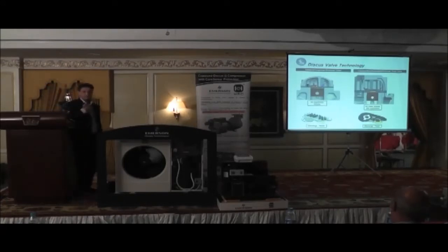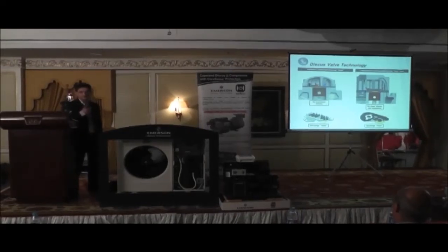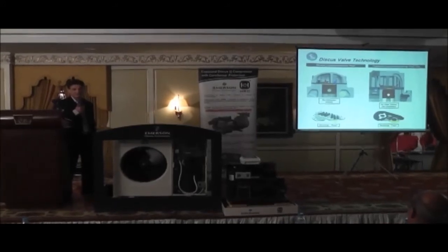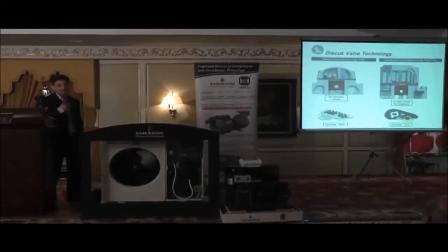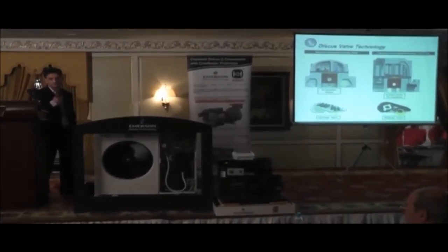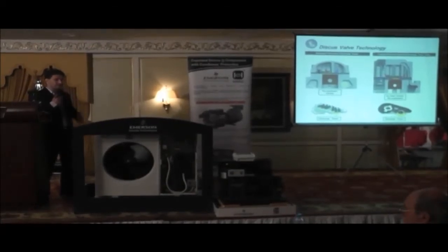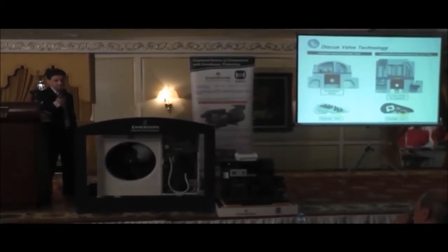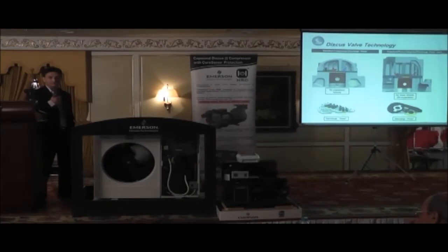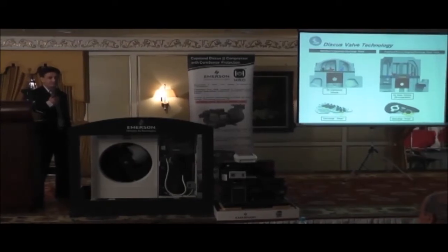So on your left-hand side, we have a standard reed compressor. On the right-hand side, the discus. The main difference between the two is that with the discus compressor, we introduce the refrigerant into the cylinder via the valve plate. So the valve plate is actually hollow. By using this design, we reduce the clearance volume, and by reducing the clearance volume, we improve the efficiency.